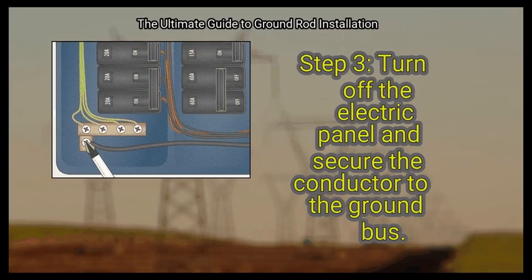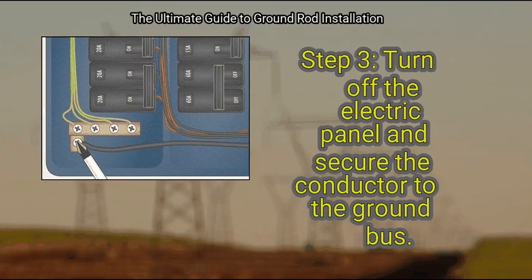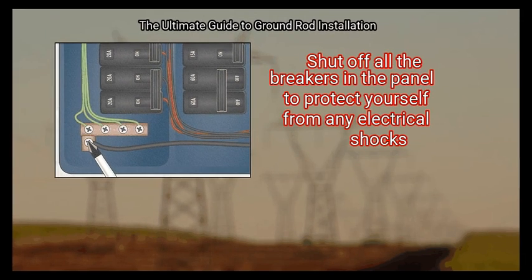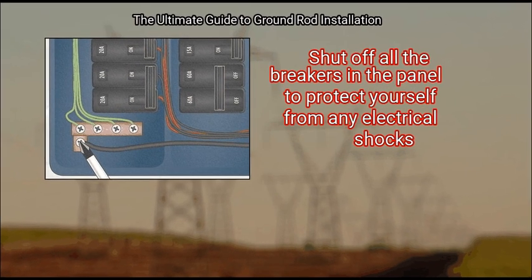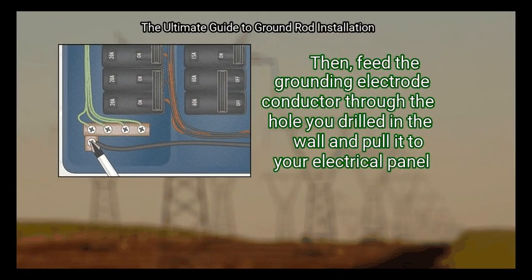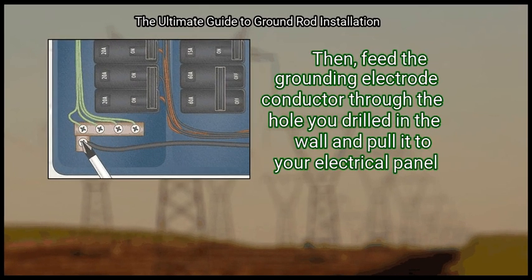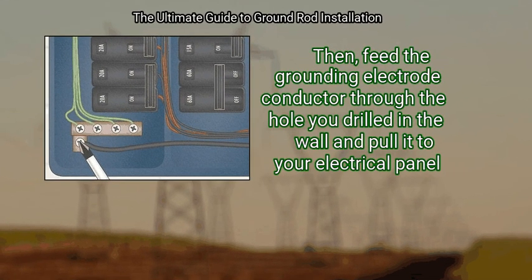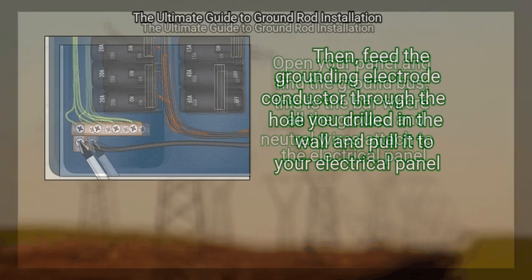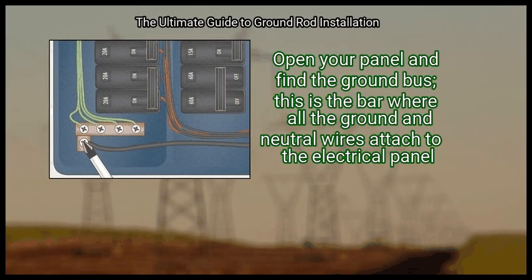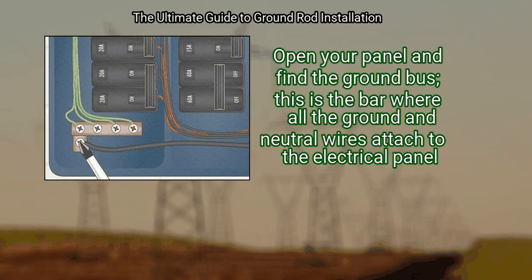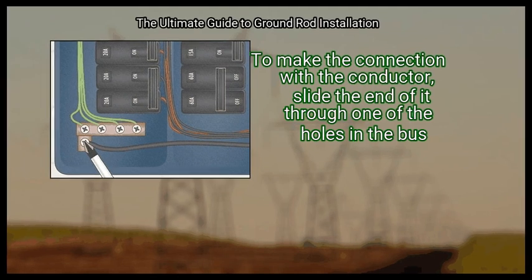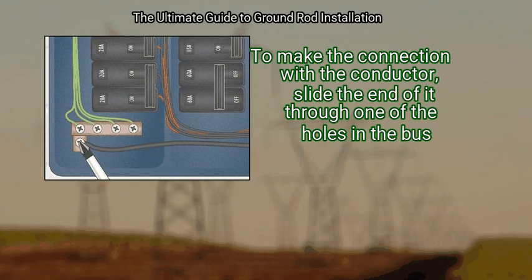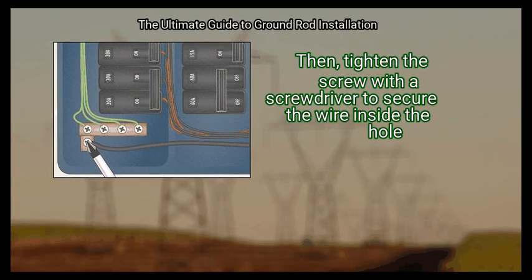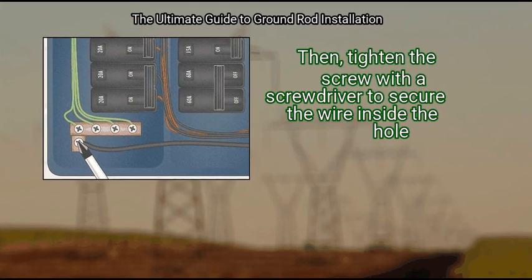Step 3. Turn off the electric panel and secure the conductor to the ground bus. Shut off all the breakers in the panel to protect yourself from any electrical shocks. Then, feed the grounding electrode conductor through the hole you drilled in the wall and pull it to your electrical panel. Open your panel and find the ground bus. This is the bar where all the ground and neutral wires attach to the electrical panel. To make the connection with the conductor, slide the end of it through one of the holes in the bus. Then, tighten the screw with a screwdriver to secure the wire inside the hole.